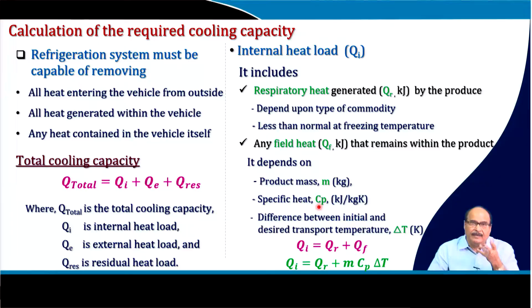Then the external heat load. External heat load Qe is the heat conducted through the floor, walls and ceilings of a transport vehicle due to the temperature difference between the inside and outside air. Solar radiation will increase the outside temperature if the vehicle is moving in open air, during the summer season, etc. So this solar radiation will increase the inside temperature if the trailer body is exposed to the sun. Then infiltration, or heat from warm air entering through small holes, cracks, drainage holes, broken door seals, and also when the doors are opened during the journey. In that process also some heat may enter inside the vehicle. So, that is the external heat Qe, and the residual heat load Qres is the heat from the air inside the trailer and heat in the insulation and inner lining of the trailer.